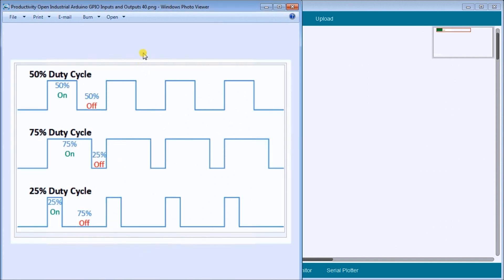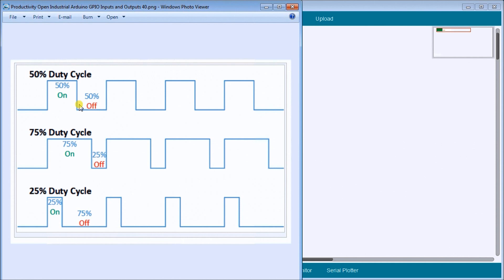Let's go back to that pulse width modulated. What we actually do is we have what we call a duty cycle. We're trying to vary the amount that we give an output in our pulse width modulated. We turn on that digital output for a duration or a duty cycle. If we have 50%, we turn on 50% of the time and off 50% of the time. Then we have 75%, it's on more than it is off. Then 25%, so it's on less than it is off. We can vary that from anywhere from 99% on to 99% off.